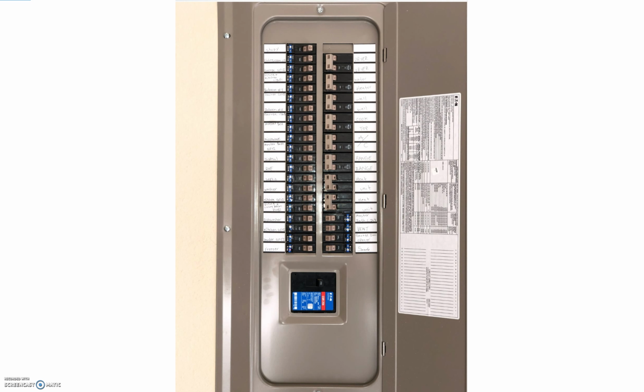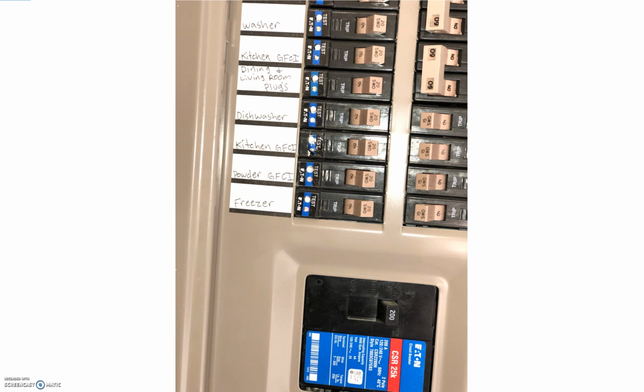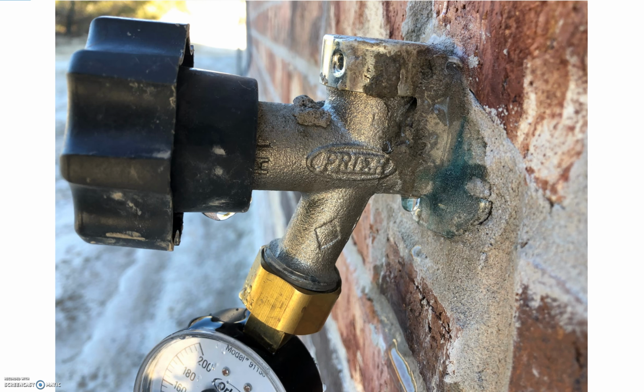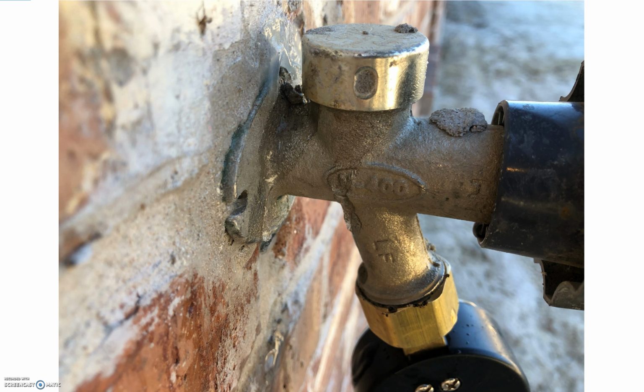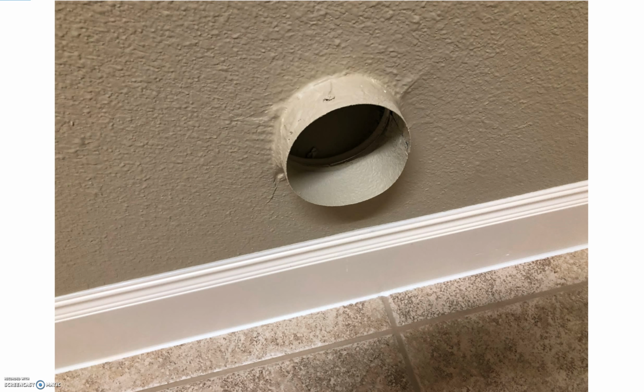This is the front of the house. This is the electrical panel. All the arc fault breakers were tested, and 3 of them did not trip, and that was the kitchen, powder bath, and the freezer GFCIs did not trip when tested. The left side hose bib or faucet and the back faucet dripped during operation.